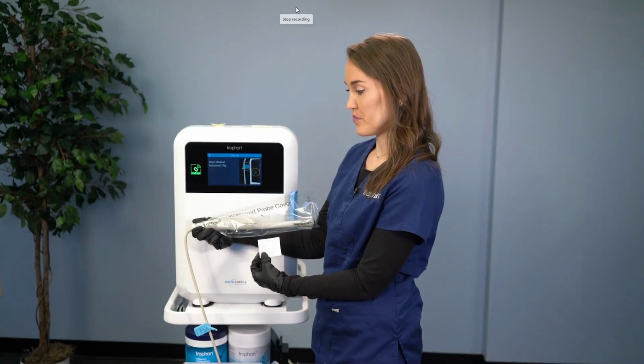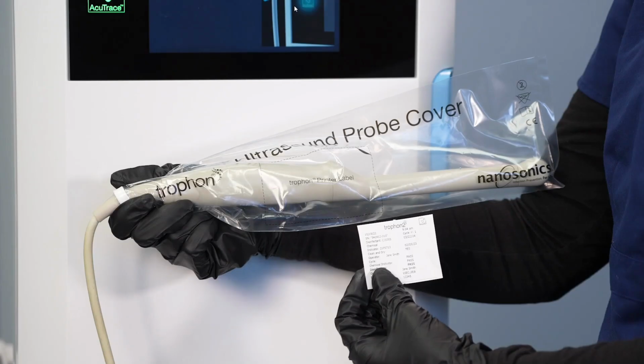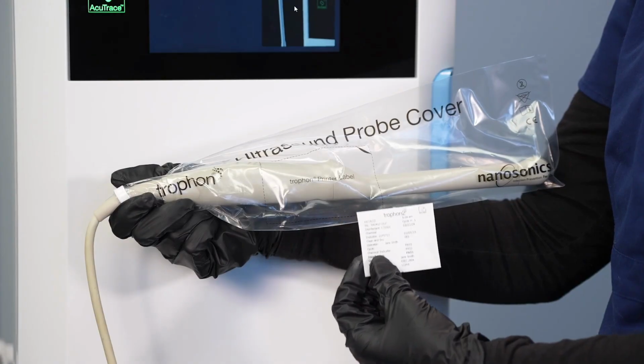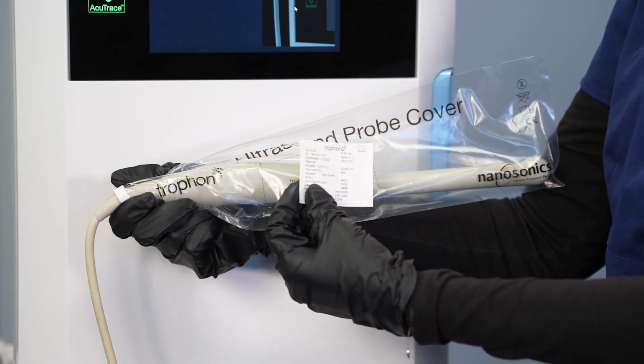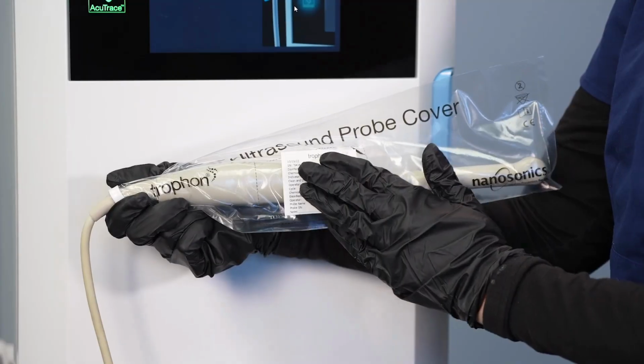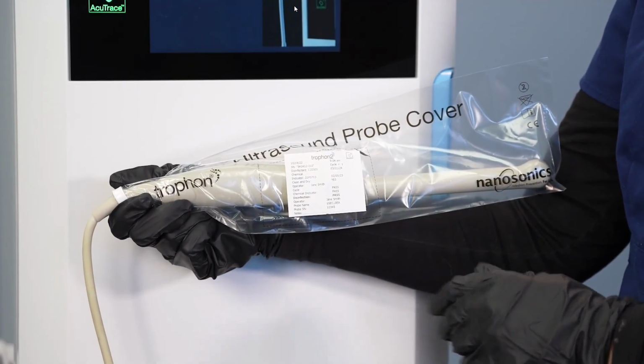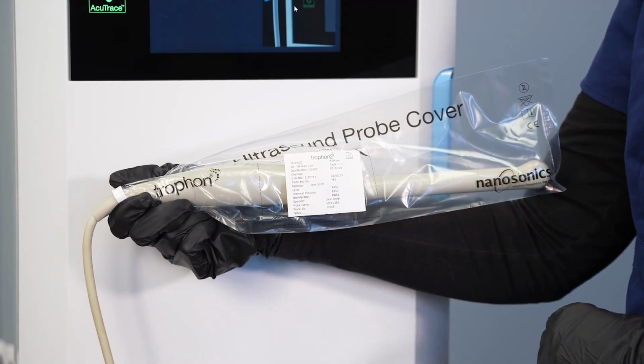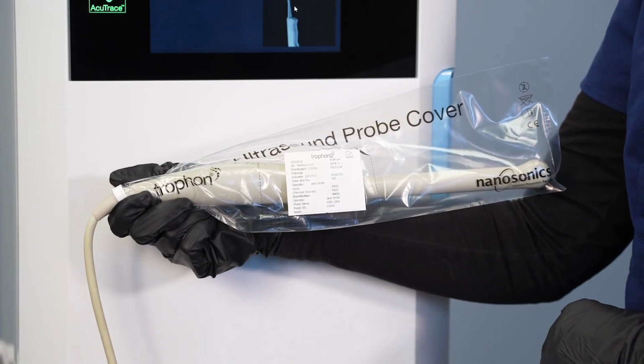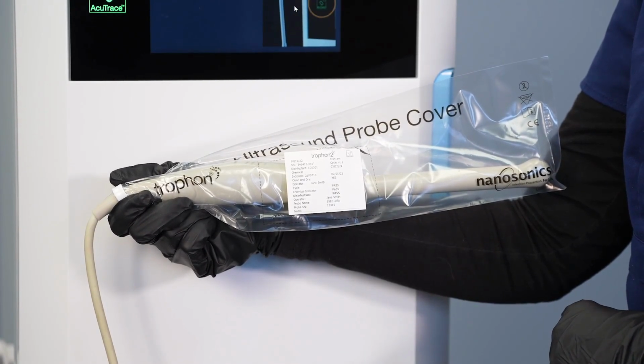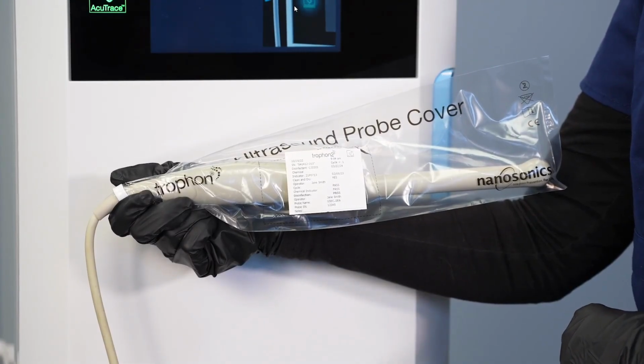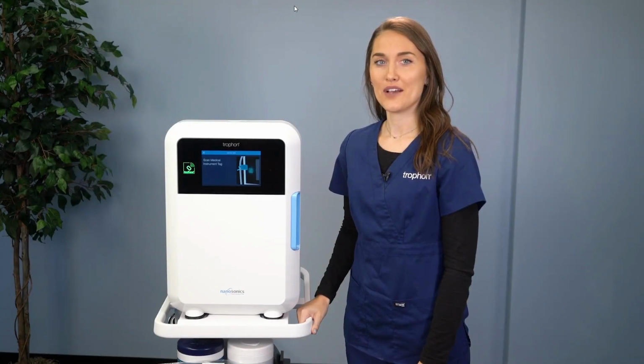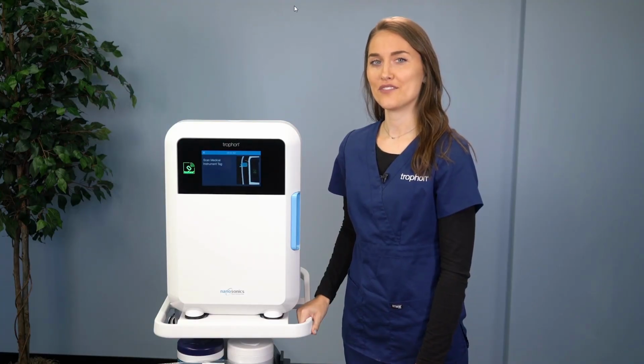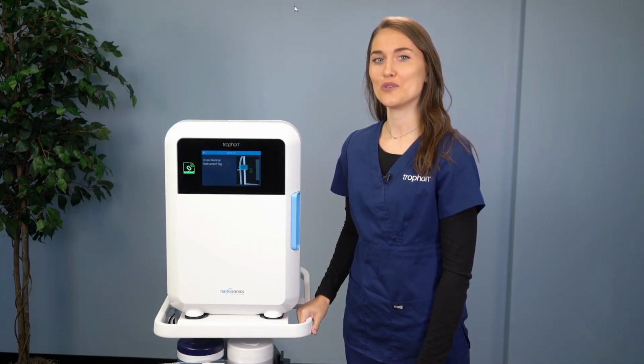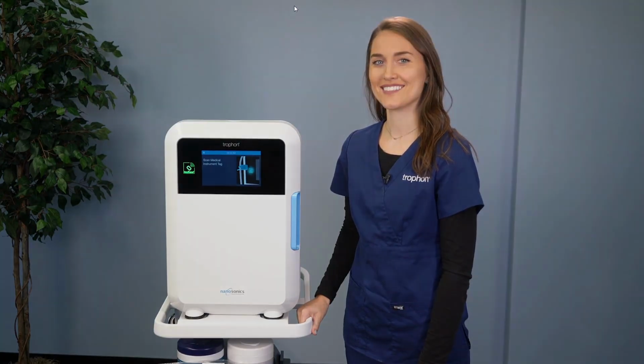Now place the first printed label on the outside of the probe cover to identify that this probe has been properly high-level disinfected. Finally, place the second printed label in your designated high-level disinfection log, along with patient identifiers per your facility's policies and procedures. You have now completed a successful high-level disinfection cycle of an ultrasound probe utilizing the Trophon2 device.